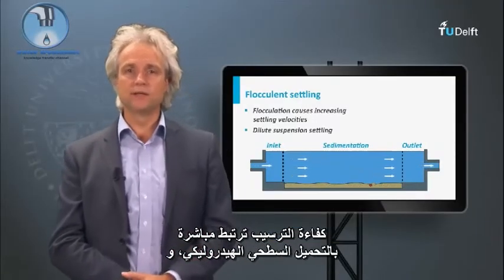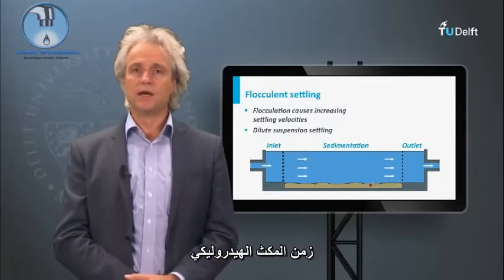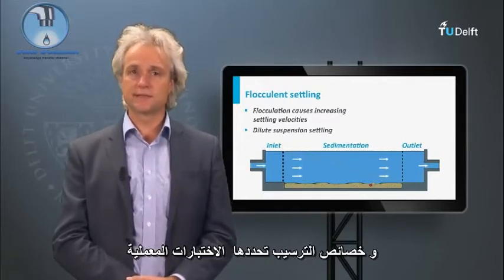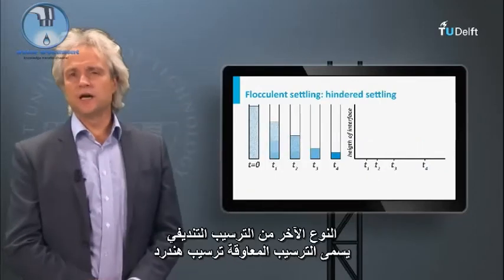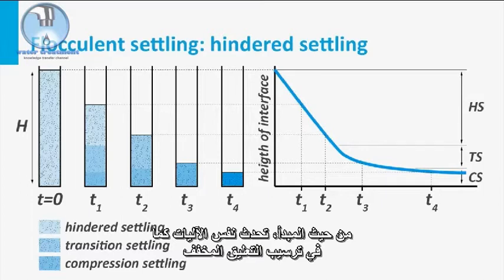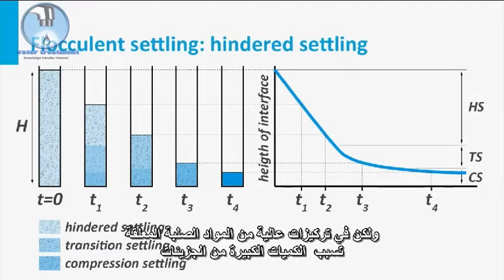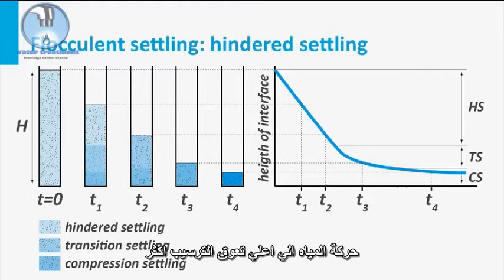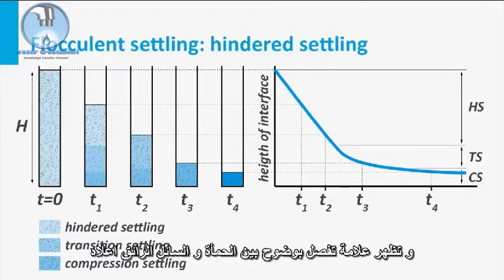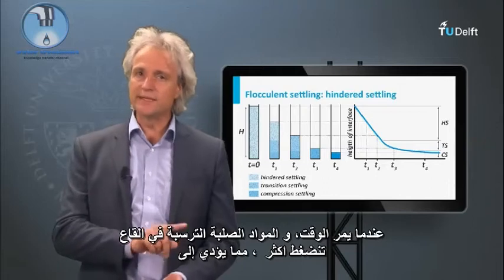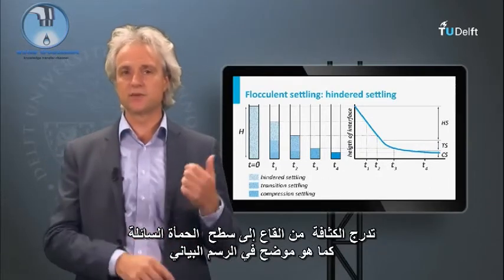The settling efficiency is directly related to the hydraulic surface load and the hydraulic retention time. There are no mathematical formulas to describe the process, and sedimentation characteristics are determined by laboratory tests. The other type of flocculent settling is the so-called hindered settling. In principle, the same mechanisms occur as in dilute suspension settling, but at high suspended solids concentrations, the large quantities of particles cause multiple interactions, resulting in a slow downward movement of particles. The upward water movement further hinders settling. A clearly marked interface between sludge and supernatant liquid occurs. When time passes, the settled solids at the bottom further compress, leading to a density gradient from the bottom to the sludge-liquid interface, as illustrated in this graph.